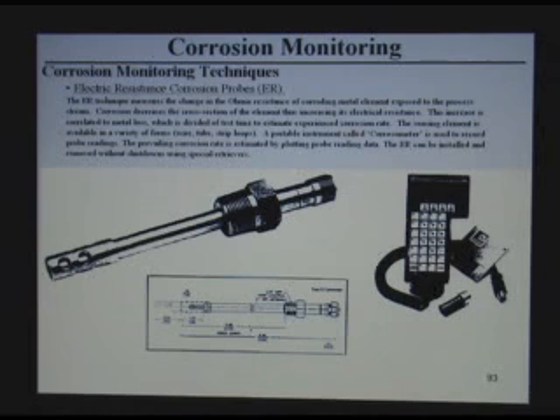When this wire is inserted in the surface, it starts corroding, so the cross section of the wire becomes smaller and the electric resistance becomes higher. From this change in electric resistance, you can correlate that to the corrosion rate. That's why they call it the electric resistance probe.